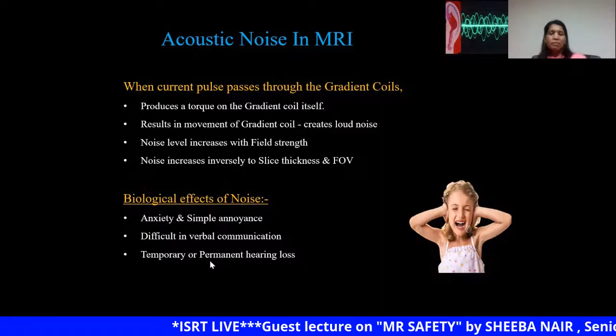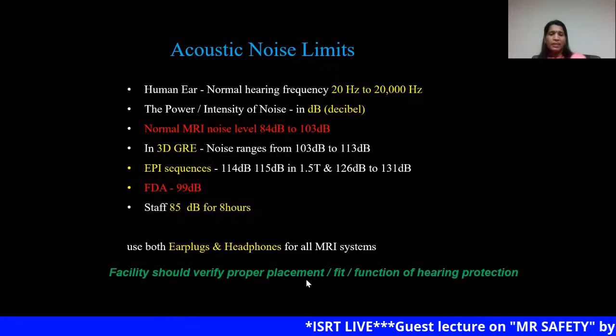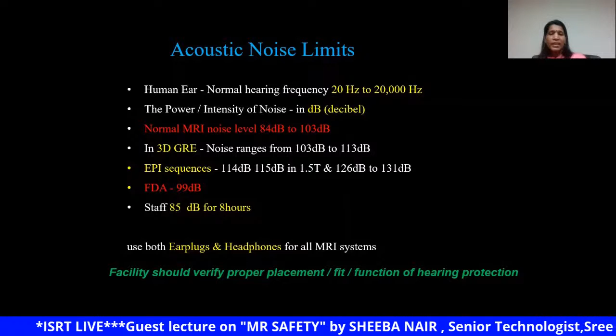The noise level is also regulated by the FDA. It has put a limit: 99 decibels is the upper limit for noise that is considered safe for the patient. But all MR systems are capable of producing noise levels greater than 99 decibels, especially the echoplanar imaging sequence. It produces an auditory noise level above the approved limit. So the recommendation is that the MR facility should provide earplugs or headphones to all patients undergoing MR examination. Before the examination, we should also verify that these ear protecting devices are properly placed, fit well, and are functioning properly before starting the examination.